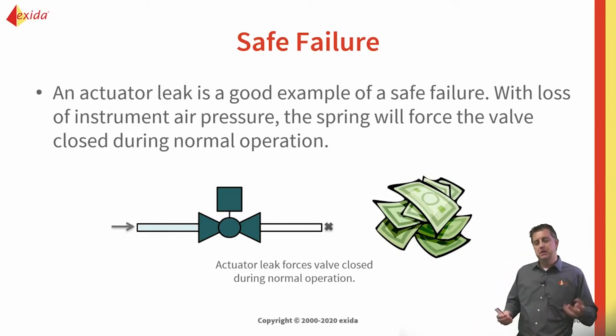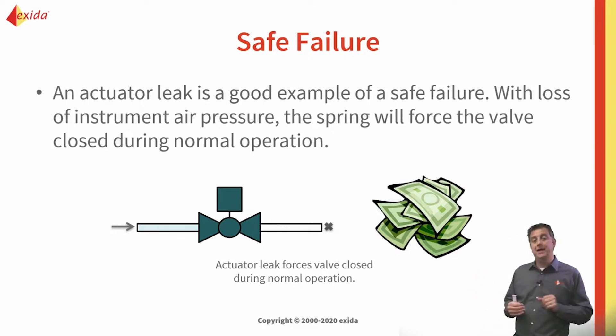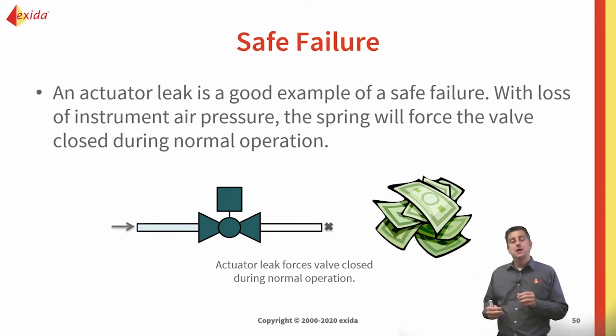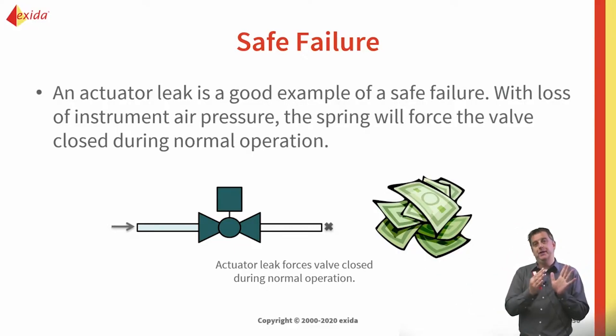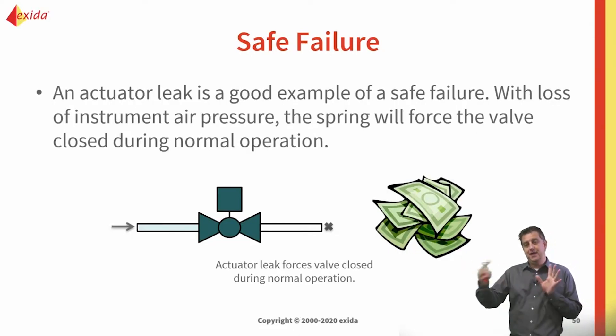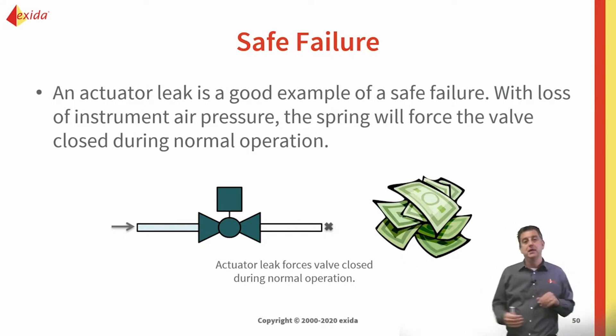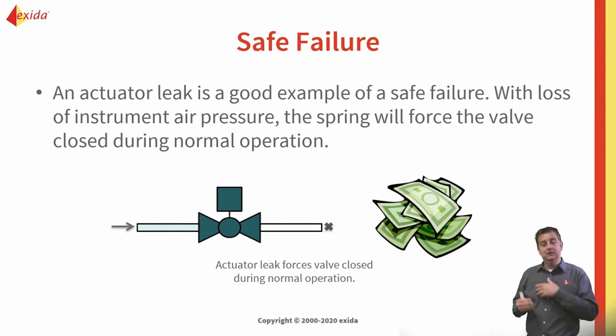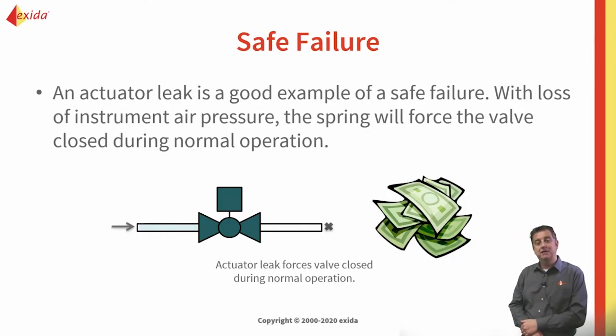A typical example is a spring return actuator where we put pressure to open the valve and compress the spring. If for whatever reason there's a leak in that air chamber and the actuator can no longer hold pressure on the spring, the spring will simply expand and bring the valve to the safe position. That's an example of a safe failure.